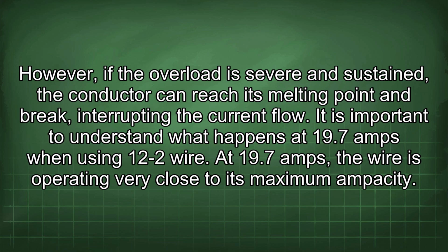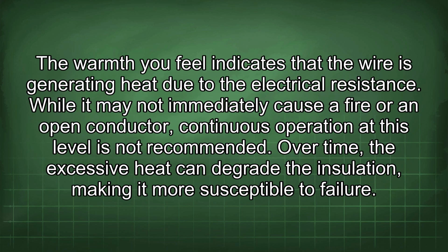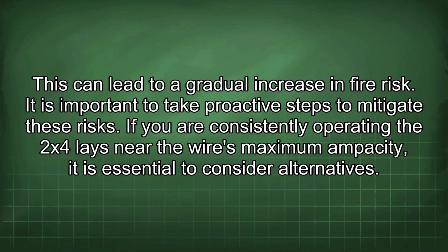It is important to understand what happens at 19.7 amps when using 12-2 wire. At 19.7 amps, the wire is operating very close to its maximum ampacity. The warmth you feel indicates that the wire is generating heat due to the electrical resistance. While it may not immediately cause a fire or an open conductor, continuous operation at this level is not recommended. Over time, the excessive heat can degrade the insulation, making it more susceptible to failure. This can lead to a gradual increase in fire risk. It is important to take proactive steps to mitigate these risks.